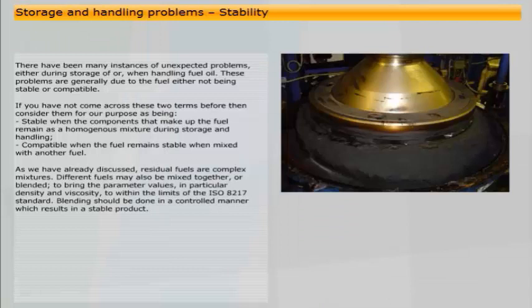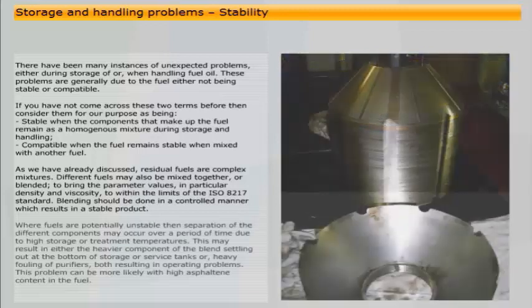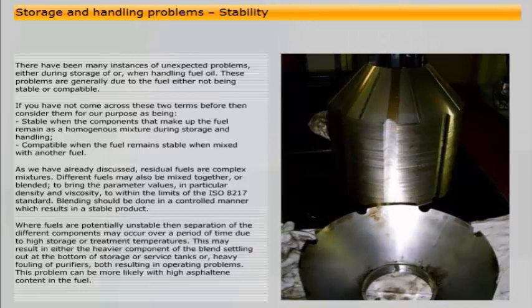As we have already discussed, residual fuels are complex mixtures. Different fuels may also be mixed together or blended to bring the parameter values, in particular density and viscosity, to within the limits of the ISO 8217 standard. Blending should be done in a controlled manner which results in a stable product. Where fuels are potentially unstable, then separation of the different components may occur over a period of time due to high storage or treatment temperatures. This may result in either the heavier component of the blend settling out at the bottom of storage or service tanks, or heavy fouling of purifiers, both resulting in operating problems. This problem can be more likely with high asphaltene content in the fuel.